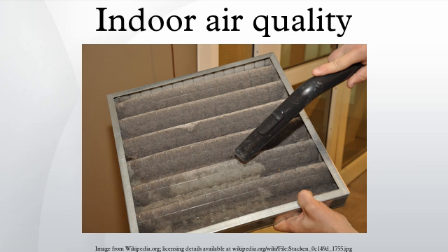In the USA, and according to ASHRAE standards, ventilation in classrooms is based on the amount of outdoor air per occupant plus the amount of outdoor air per unit of floor area, not air changes per hour. Since carbon dioxide indoors comes from occupants and outdoor air, the adequacy of ventilation per occupant is indicated by the concentration indoors minus the concentration outdoors. The value of 615 ppm above the outdoor concentration indicates approximately 15 cubic feet per minute of outdoor air per adult occupant doing sedentary office work, where outdoor air contains 385 ppm, the current global average atmospheric CO2 concentration.